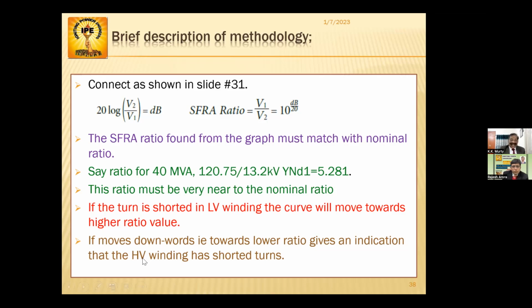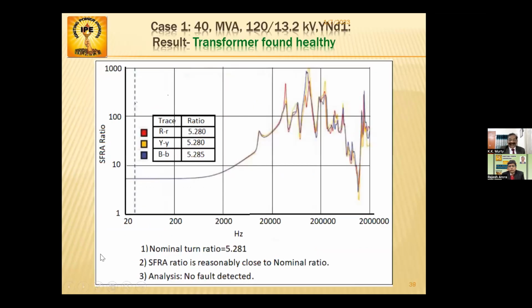Okay. In the other case, when a lower ratio is given, it is an indication that the HV winding has shorted turns. HV winding is in the numerator, and LV winding is in the denominator. So if the numerator turns are less, since the number of turns is shorted, the curve goes towards the lower side. This is what is shown in the subsequent curves.